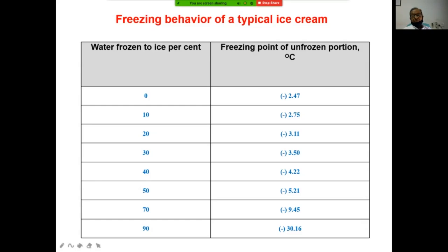So when we calculate the refrigerant load for the continuous ice cream freezer, first we should know the properties of the ice cream mix and the outlet temperature. On the basis of the outlet temperature, we can say how much water is frozen, and we can calculate the latent heat load on the basis of this percentage only. Even at minus 30 degrees, it is only 90% frozen, not 100%. Generally, we say the ice cream is frozen at minus 18 degrees and stored at minus 18 degrees centigrade. The ice cream core temperature is minus 18 degrees. It is stored at minus 23 degrees, so we can maintain the core temperature at minus 18 degrees. So it is not 100% frozen. Only then can we do scooping.